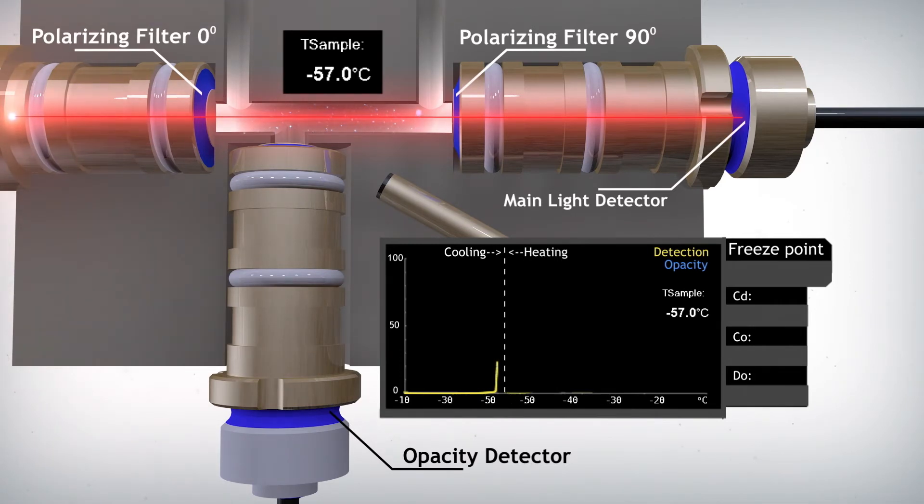Jet fuel hydrocarbon crystals are anisotropic crystals, which means the polarized light from the laser will be scattered in all directions and will allow light into the main detector, resulting in a signal which is recorded on the graph. As the crystals grow larger, the scattered light is strong enough to elicit a signal on the opacity detector.